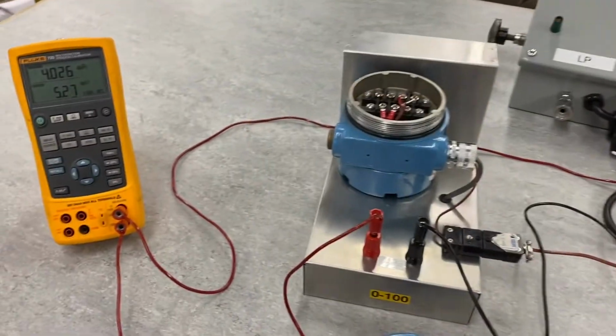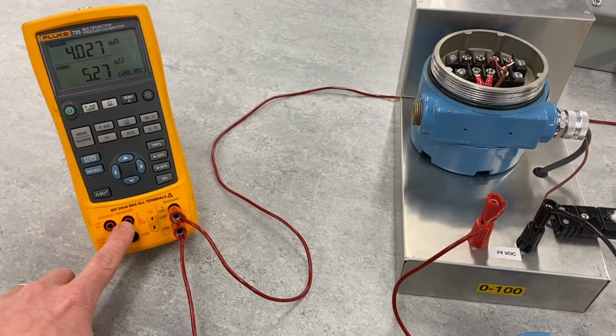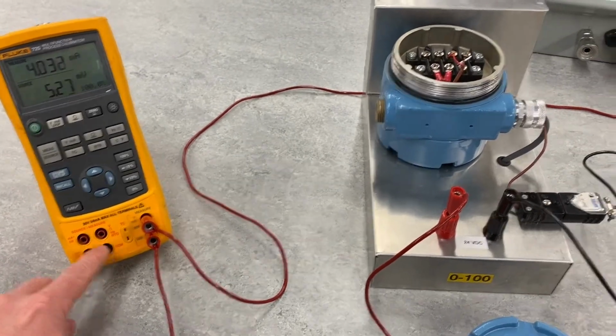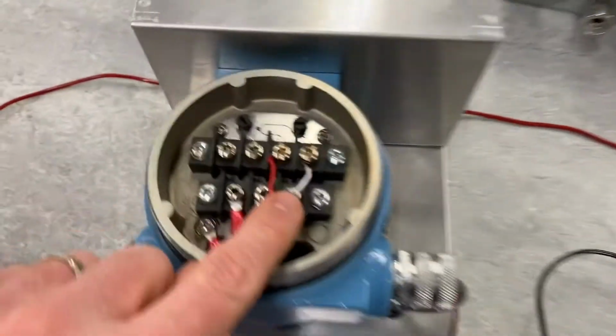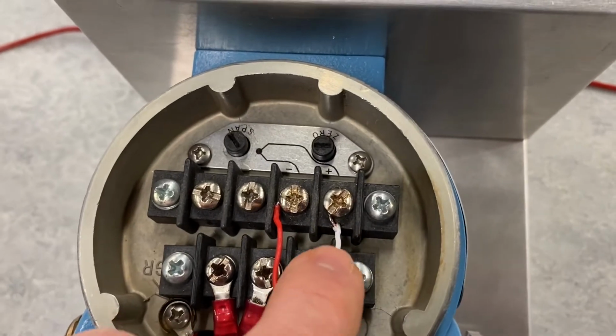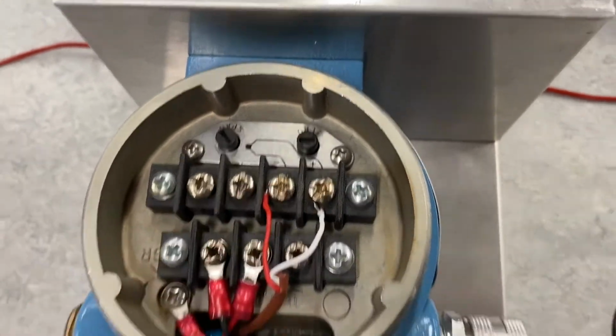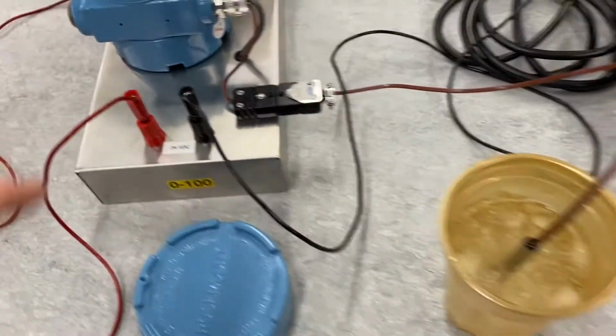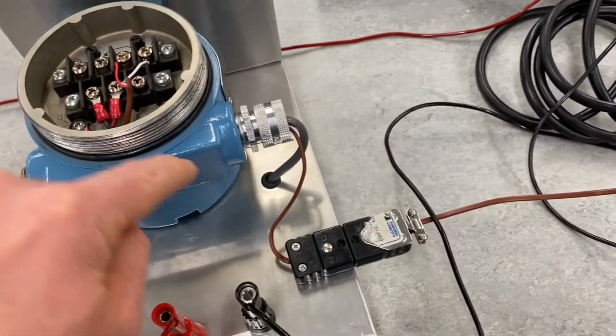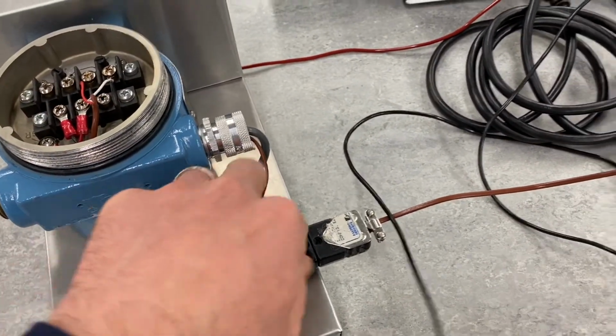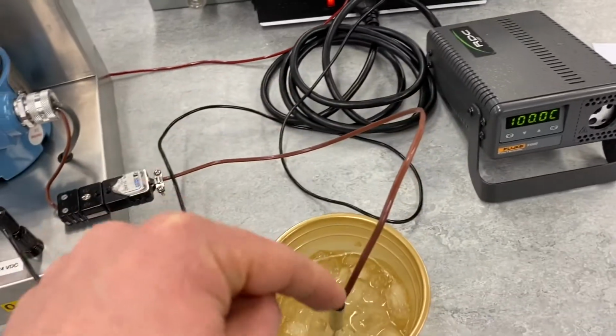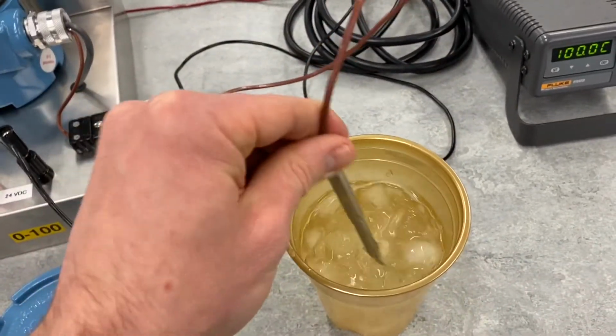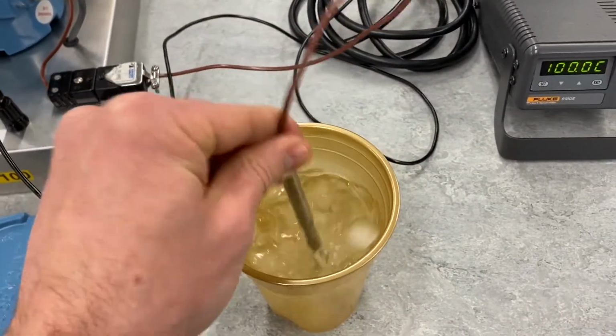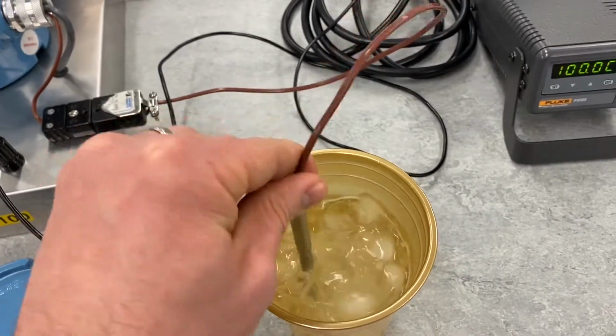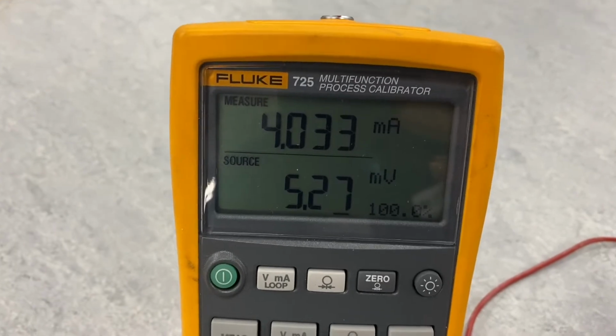All right, so now I've removed the millivolt input into our transmitter, and connected the thermocouple directly to the transmitter here, the white lead going to the positive, red lead going to the negative of the type J thermocouple. This wiring then flows out of our transmitter into this thermocouple connector, and then the measuring junction of the thermocouple is down here in the ice bath. So with me agitating this now at 0 degrees C, this ice bath should be at 0 degrees C. Our transmitter is reading pretty close to the 4 milliamps.